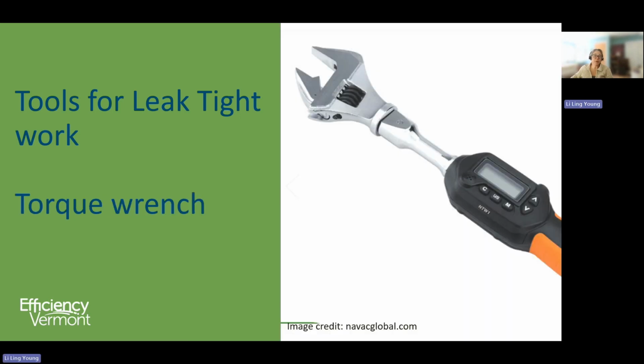And then finally, a perfect flare is tightened to the specification of the manufacturer of the flare nut. It can vary a lot over different size tubing, so tightening by feel is absurd. If you think you're doing a good job, but you're not using a torque wrench, well, you're not doing a good job.